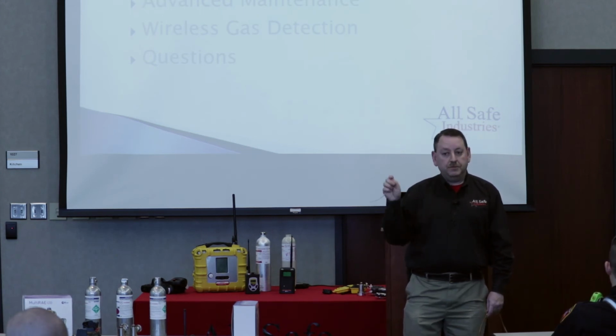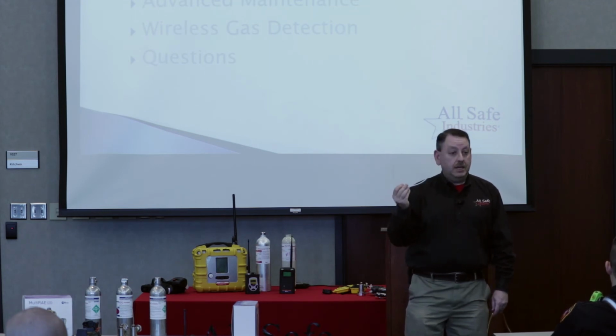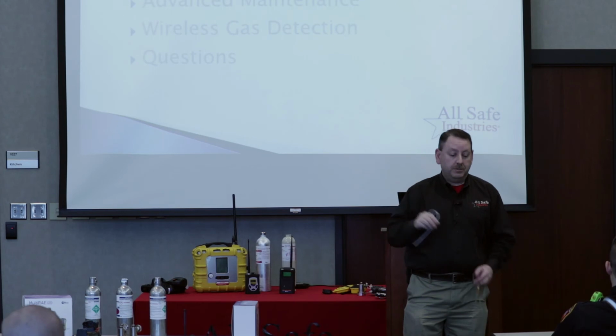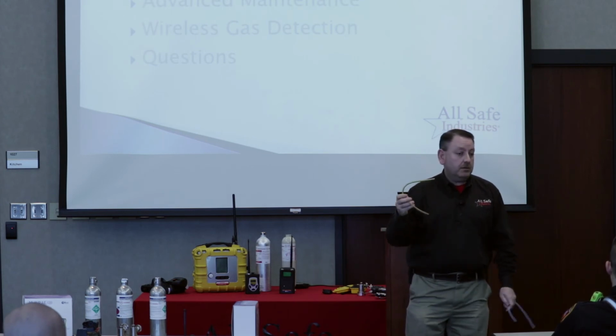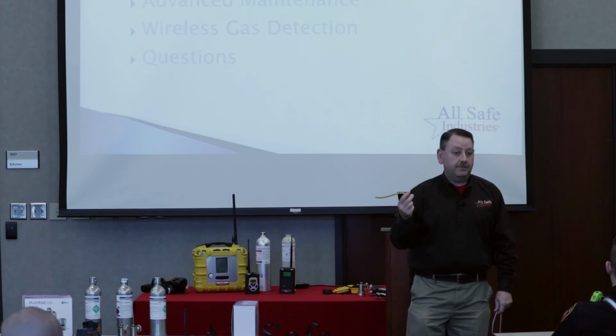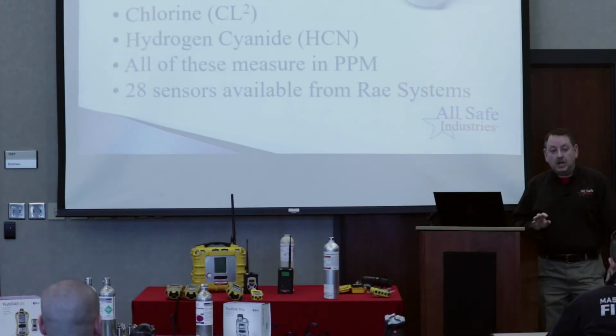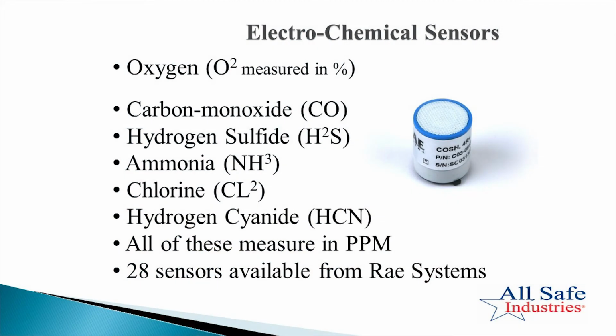Okay? So if you're on a VOC run, a hazmat run, you're going to want to use Teflon tubing. It's the opaque tubing. If you're just doing everyday, common confined space type entries, then the normal clear Tygon tubing is fine. Okay? So next, I wanted to talk about the sensors, because the sensors are what detect the gas inside the instrument, and there's about 28 different sensors that you can choose from with RAE Systems.